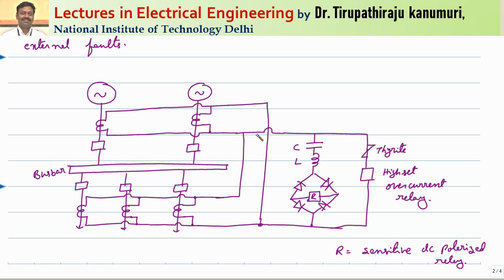These are the incoming CTs and these are the outgoing CTs. Whenever the external fault happens, current is passing in both primary and secondary, but because of differences in CT characteristics, circulating currents will pass. Only the fundamental components of those circulating currents are allowed to pass through this relay. The relay has an LC tuned circuit, tuned to operate only for the fundamental component — that is, the 50 Hz frequency component. A bridge circuit is used and the relay R is a sensitive DC polarized relay, which will operate only for a particular polarity or type of current.